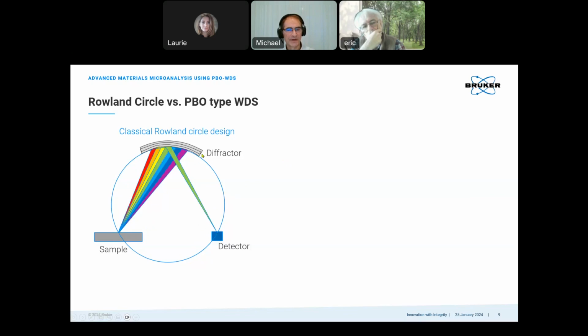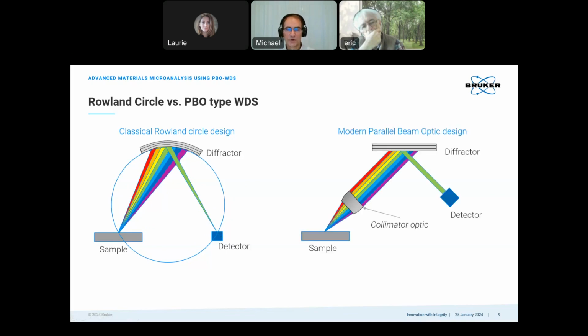So whenever the angle of the diffractor changes to reflect a different X-ray energy towards the detector, the diffractor has to move along the circle also, and the detector as well. And only that will guarantee that the focus is right in the detector. A more advanced system is using a collimator optic. This collimator optic captures a maximum of X-rays close to the source of origin, close to the sample. And the diverging X-ray beam is then converted into a parallel beam that hits the diffractor and filters out one certain energy. The main difference between the two systems is the solid angle.